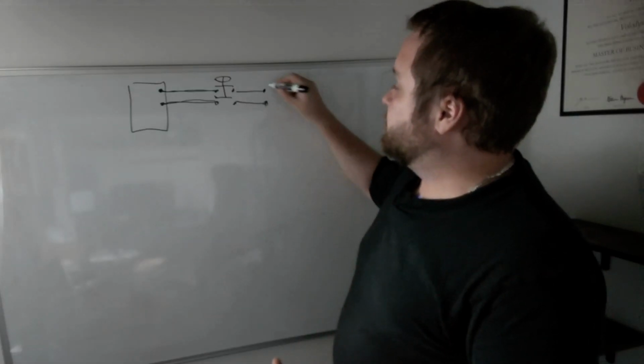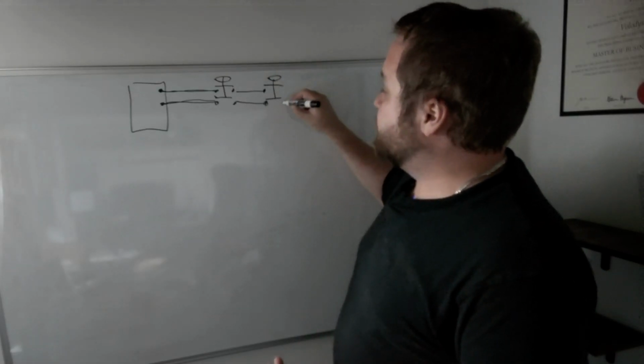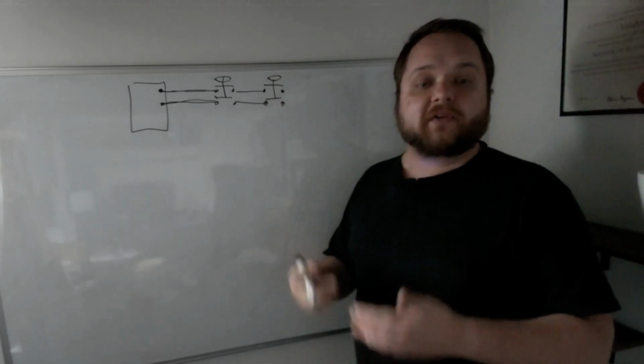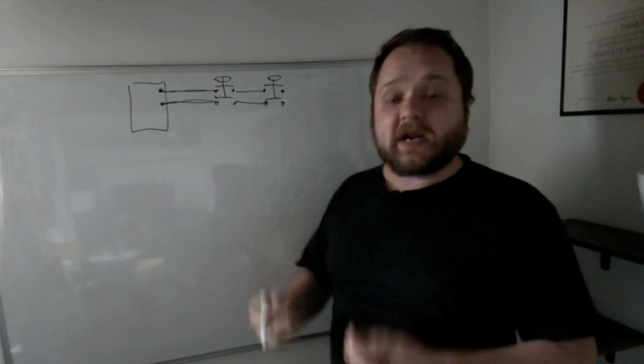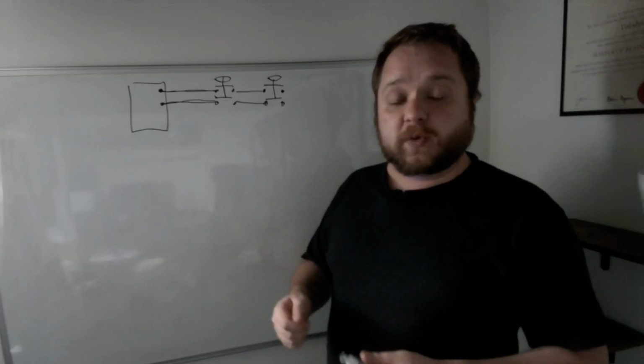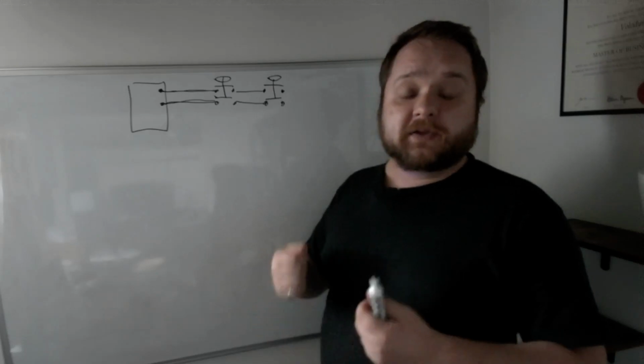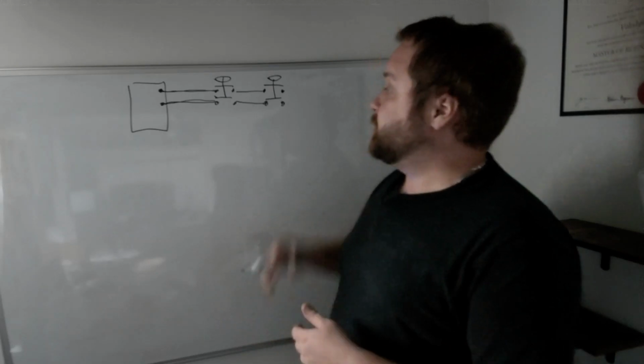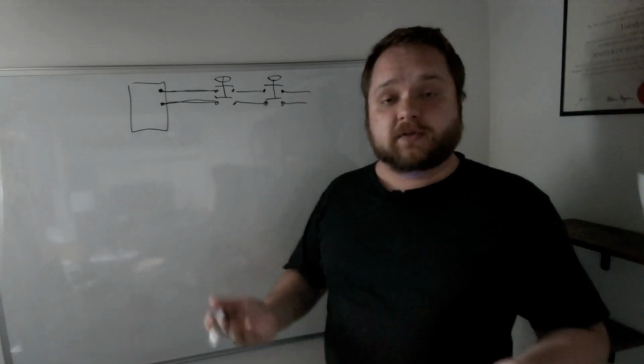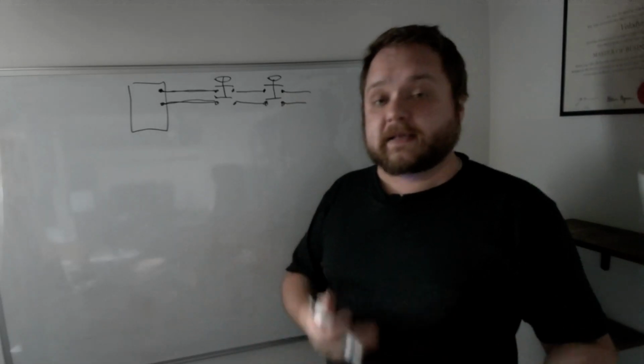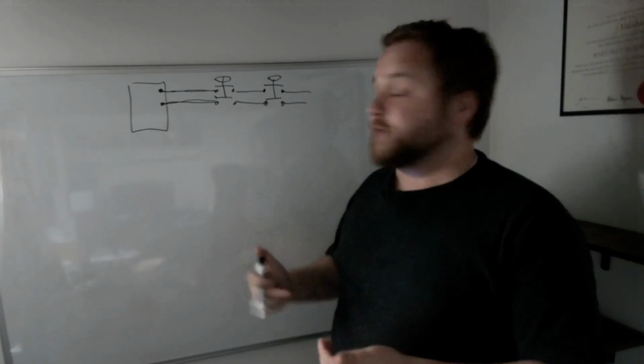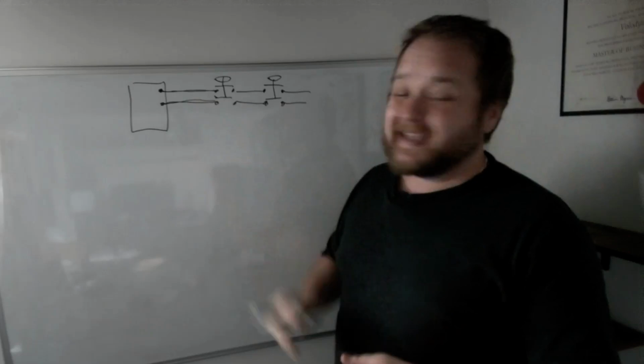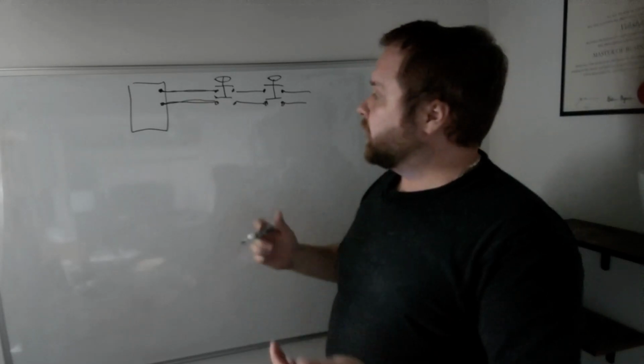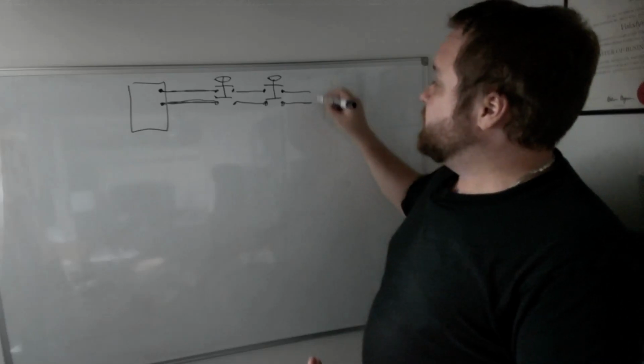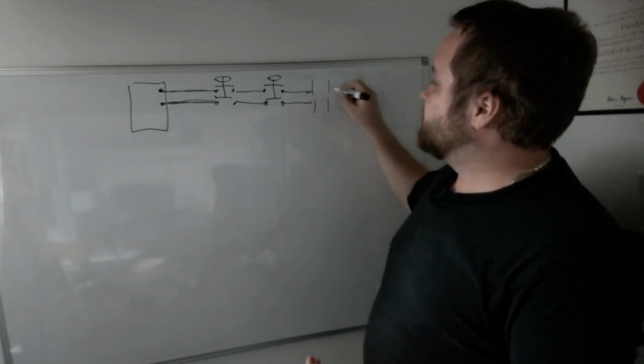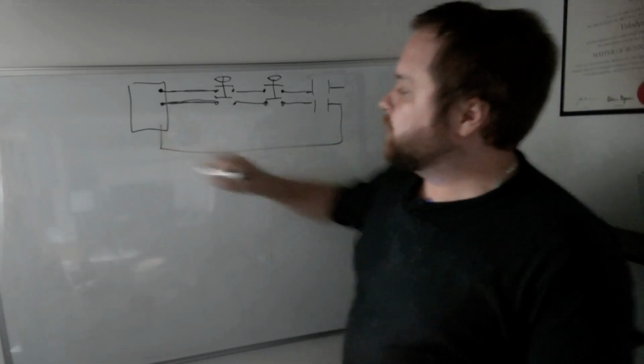And the reason why, and obviously once it's explained, it's a little bit obvious, is you don't want to have a single point of failure within your circuit. So for example, if you have a regular push button or a regular selector switch, those contacts may fail and basically close the circuit without your ability to push that button, and they will cause the safety circuit to confirm that everything's okay when in reality it is not. Therefore, it is extremely important to use dual channel safety devices with a dual channel safety relay when working in safety circuits. As you can see, now I need to maintain basically 2 points of failure in all of my circuitry. And here I'm going to just bring this back.